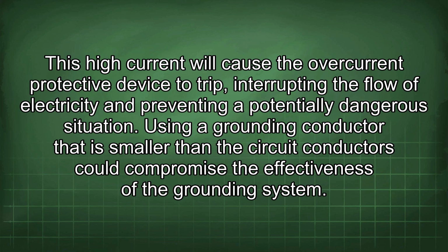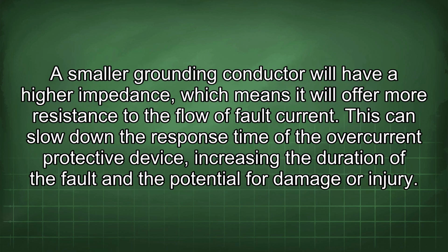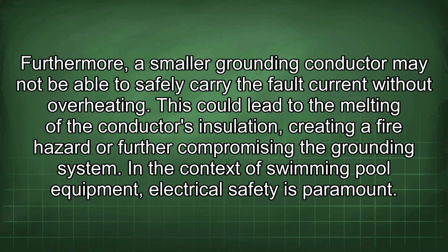dangerous situation. Using a grounding conductor that is smaller than the circuit conductors could compromise the effectiveness of the grounding system. A smaller grounding conductor will have a higher impedance, which means it will offer more resistance to the flow of fault current. This can slow down the response time of the overcurrent protective device, increasing the duration of the fault and the potential for damage or injury. Furthermore, a smaller grounding conductor may not be able to safely carry the fault current without overheating. This could lead to the melting of the conductor's insulation, creating a fire hazard or further compromising the grounding system.